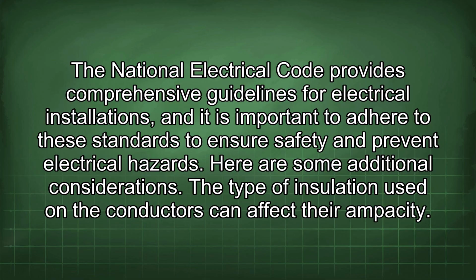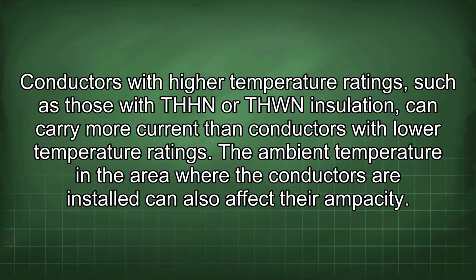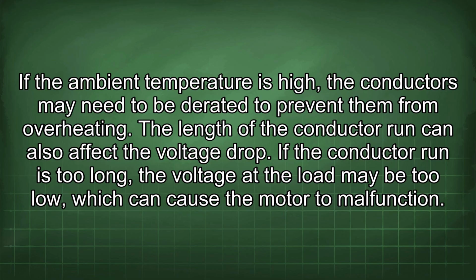Here are some additional considerations. The type of insulation used on the conductors can affect their ampacity. Conductors with higher temperature ratings, such as those with THHN or THWN insulation, can carry more current than conductors with lower temperature ratings. The ambient temperature in the area where the conductors are installed can also affect their ampacity. If the ambient temperature is high, the conductors may need to be derated to prevent them from overheating.